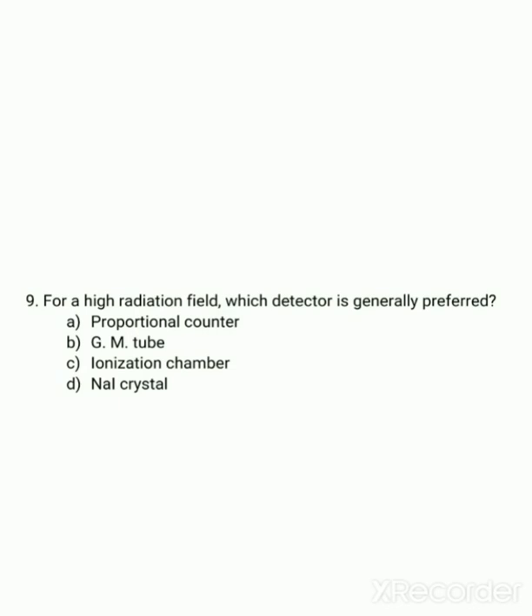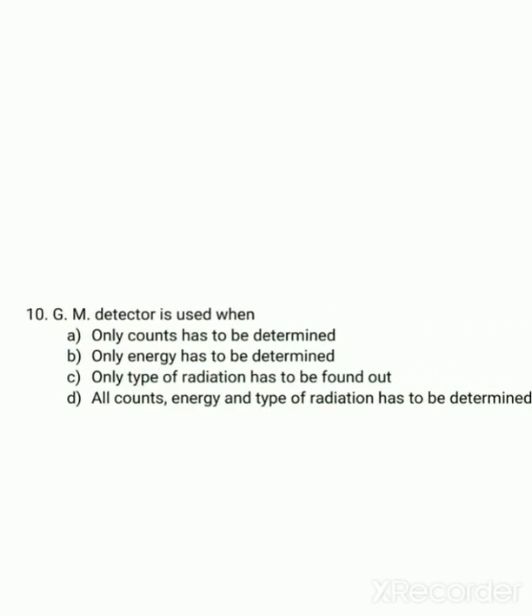The ninth question: for a high radiation field, which detector is generally preferred? In our departments, mainly two types of detectors are used — ionization chambers and GM counters — but for high radiation fields, the ionization chamber is used. We cannot measure high radiation fields using a GM detector. With a GM detector we can only determine counts; energy cannot be determined because in GM detectors an avalanche is formed, so energy information is lost. We also cannot determine the type of radiation using a GM detector. The correct answer is: only counts can be determined.